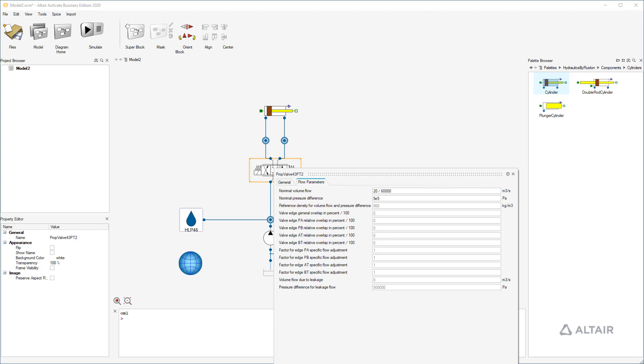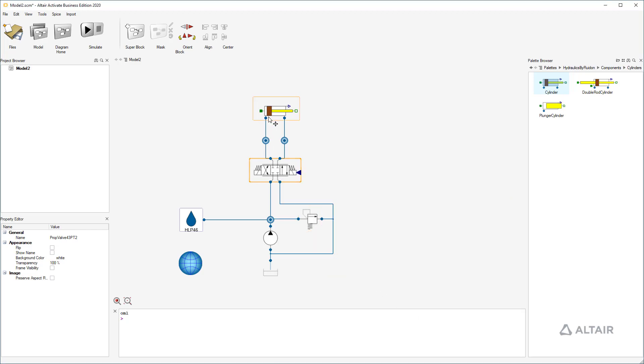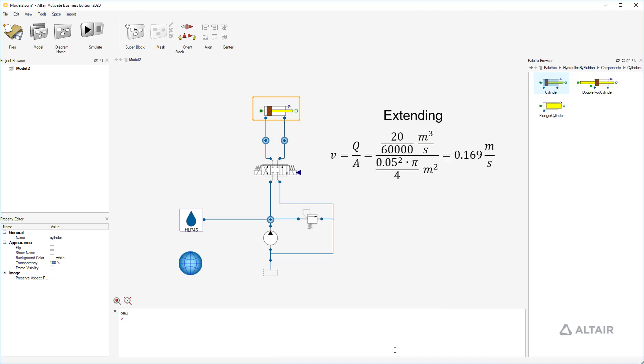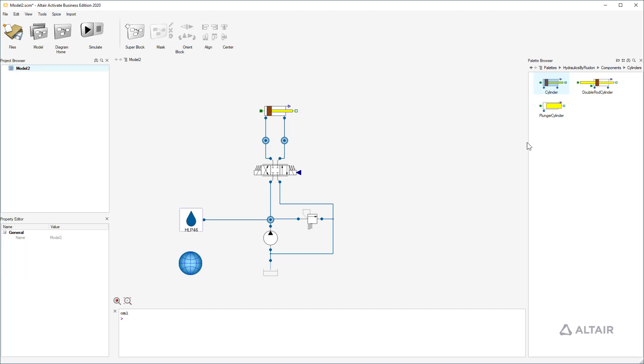At the cylinder we want to have a piston diameter of 50 mm, a rod diameter of 30 mm, a cylinder length of 1000 mm and a moved mass of 200 kg. Now we can determine the velocity of the cylinder. In extending direction it should be 169 mm per second. In retraction direction 265 mm per second given by the flow and piston area of the cylinder.